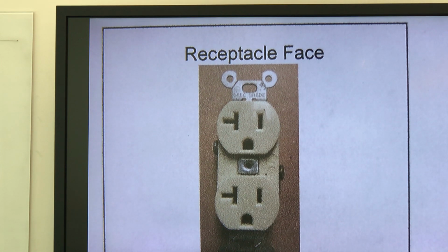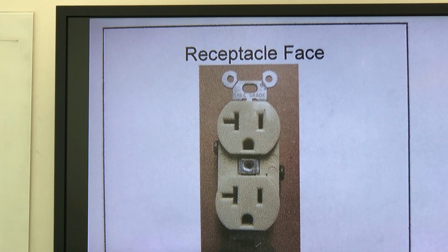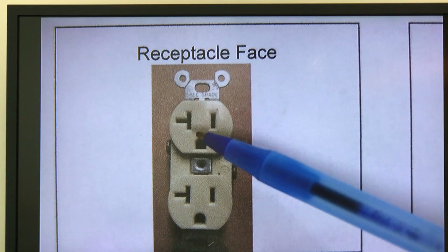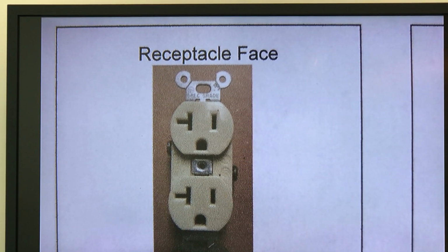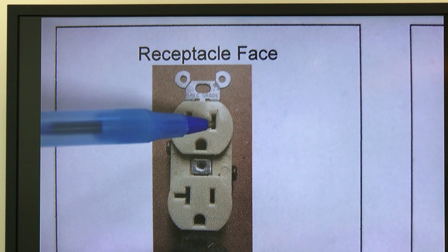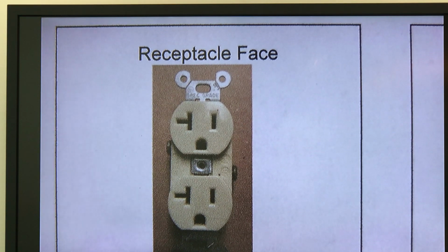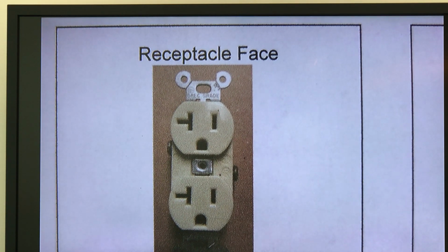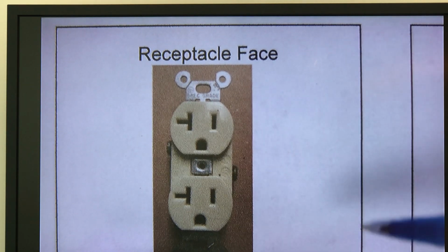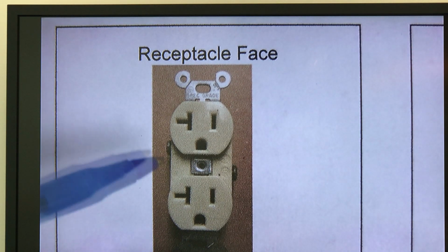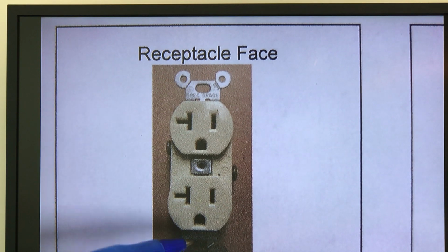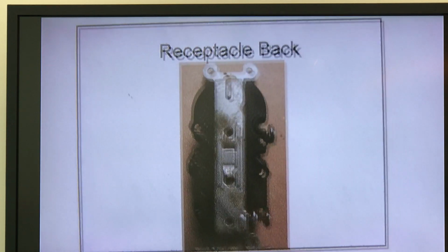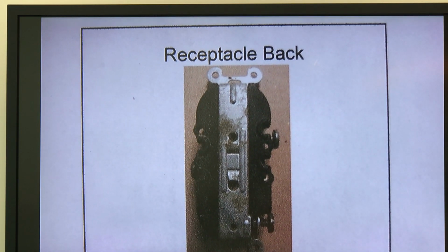Okay, so what we're looking at now is a photograph of a receptacle face. It's a 20 ampere receptacle, as you can tell, because we have the T-shaped structure over here. So again, this is the neutral, this is the hot, and these are the grounds. Think of it like a little face. If it's winking at you, the short one is the hot line, the bigger one is the neutral, this is its little mouth.